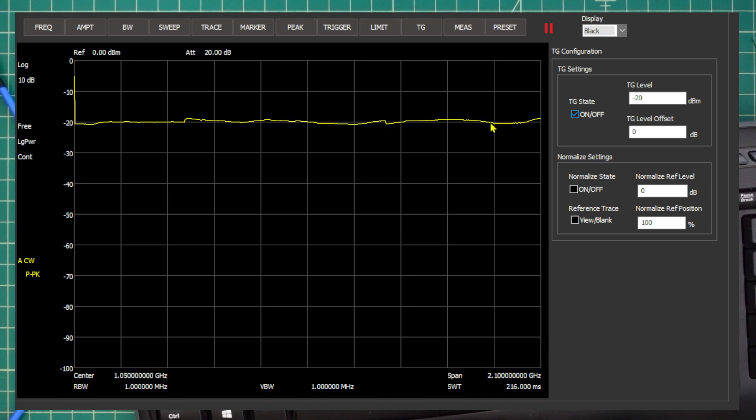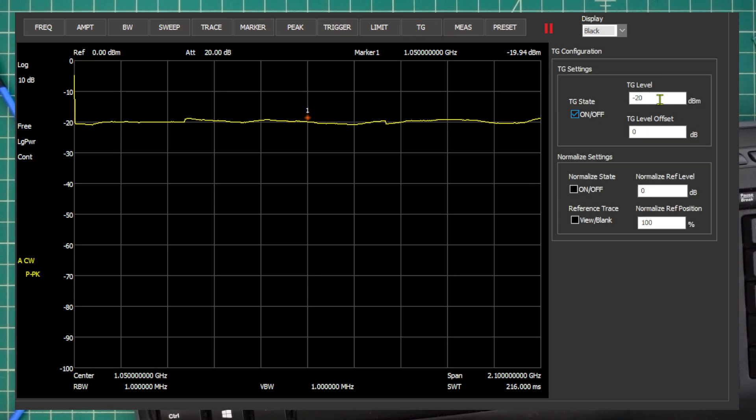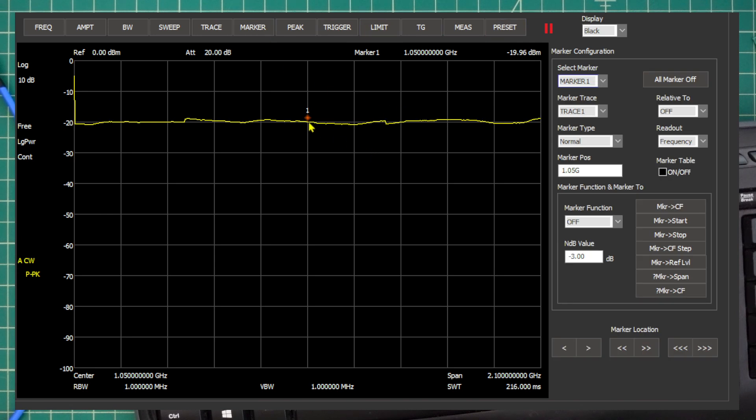Now, what we can do is we can actually normalize this. And what that will do is it will take into account for any deviations that we see in the cable. But what you can see here is that at certain frequencies, let's get a marker on here. We do have some deviation. So let's go to marker type normal. And there we have a marker type. Now, when we took a look at our tracking generator tab, our tracking generator level is negative 20 dB. And we can see over here with our marker, let's go back to the marker table.